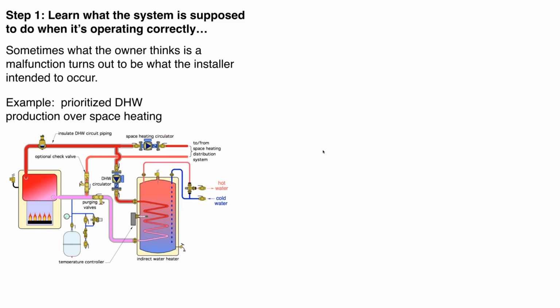A boiler that is supplying space heating and an indirect water heater, where a controller that is operating the space heating circulator or perhaps multiple zone circulators is also operating this domestic hot water circulator, but it's doing this domestic water circulator as the priority zone. In other words, when that domestic water circulator is on, it's going to turn this circulator off. And perhaps on a very cold day, depending on how long that domestic water call is on, let's say you have 2 or 3 showers happening in a row, or you have laundry, you have a big demand for domestic hot water, that domestic water tank might require heating over at least half an hour.